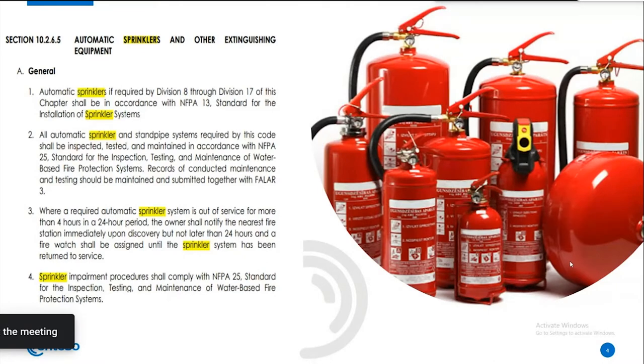Number 3: where a required automatic sprinkler system is out of service for more than 4 hours in a 24-hour period, the owner shall notify the nearest fire station immediately upon discovery, but not later than 24 hours, and a fire watch shall be assigned until the sprinkler system has been returned to service.